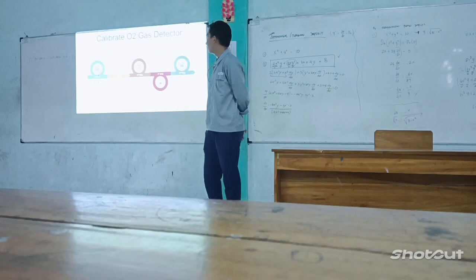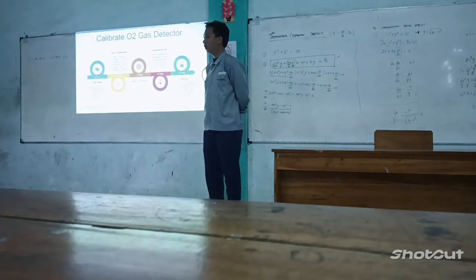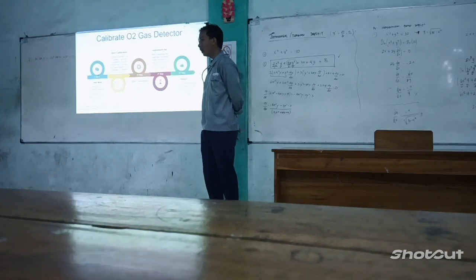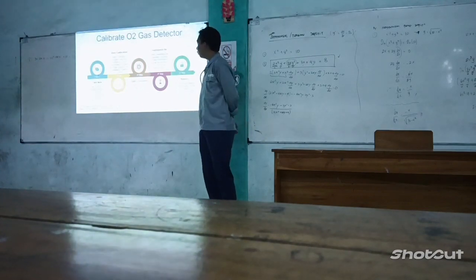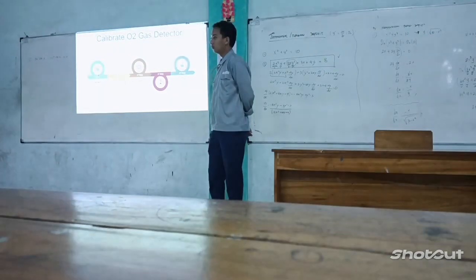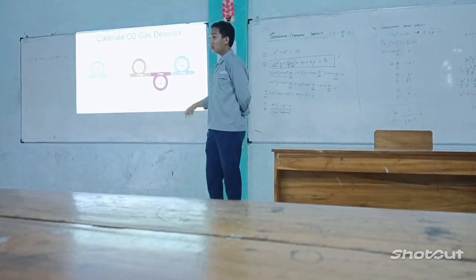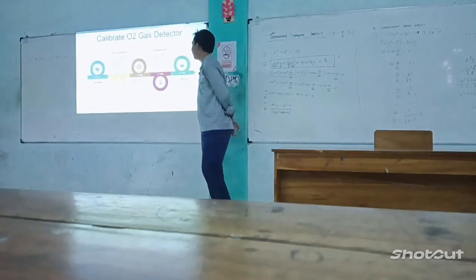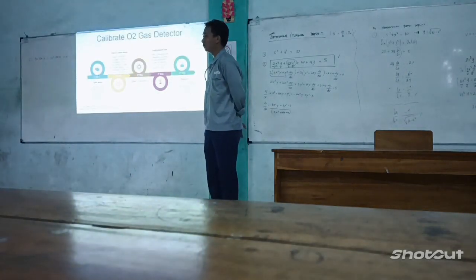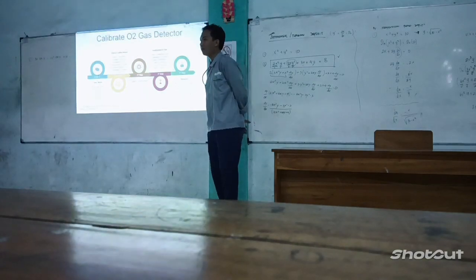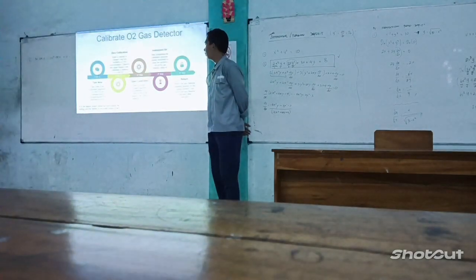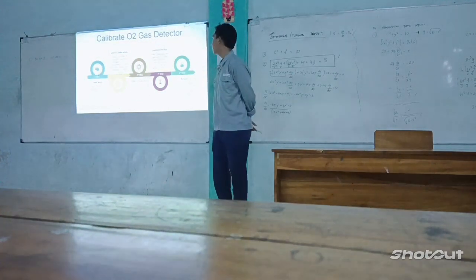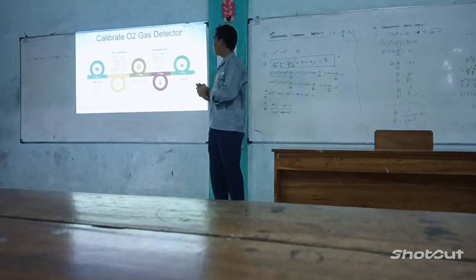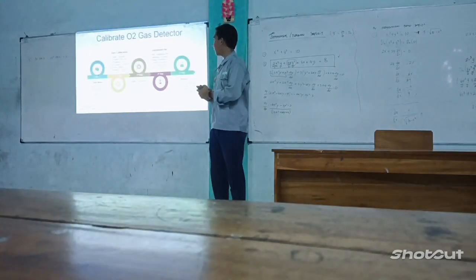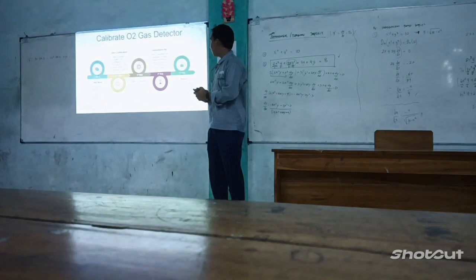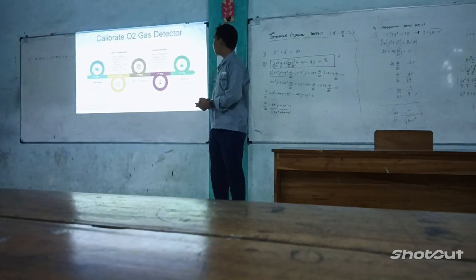Yes, but why not zero? The step is zero calibration, but we insert a sample of 2.5%. After zeroing or before zeroing? The question is lacking. Is the 2.5% scale after zeroing or before? Before. Because for every sensor we have a standard.